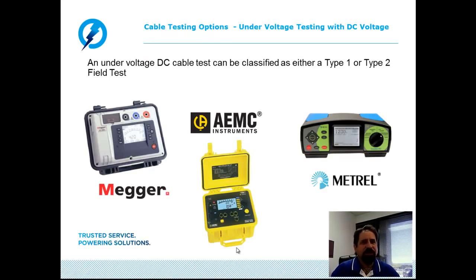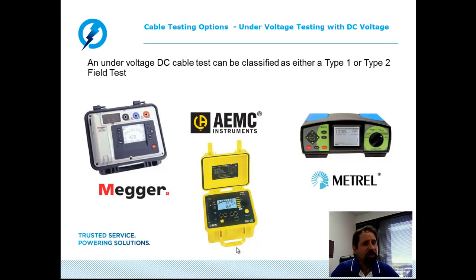Let's start with under-voltage tests utilizing DC voltage. Under-voltage tests are typically performed with a megohmmeter. Since the tests use voltages under the rating of the insulation, the test is considered non-destructive and does not produce the ill effects associated with high-voltage DC tests. Tests can be either a Type 1 pass-or-fail test, or used as a diagnostic Type 2 style test. Diagnostic insulation tests electrically stimulate the insulation and measure the response, allowing conclusions to be drawn about the condition or overall health of the insulation.